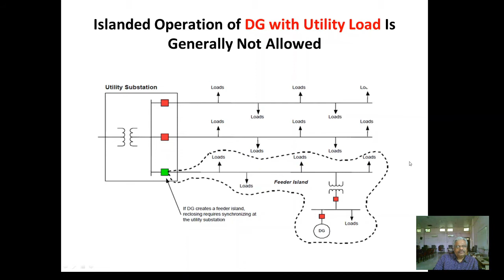And when this distributed generation is supplying load on the distribution system, you call it an unintentional island. If DG creates a feeder island, reclosing requires synchronizing at the utility substation. This causes many problems also. What are those problems, or why is this unintentional island not accepted or not allowed? We will see that. But here we can see that when the circuit breaker opens, this island gets formed, and this is not accepted because it is feeding load, or it is feeding in the direction also. We'll see the reasons one by one.